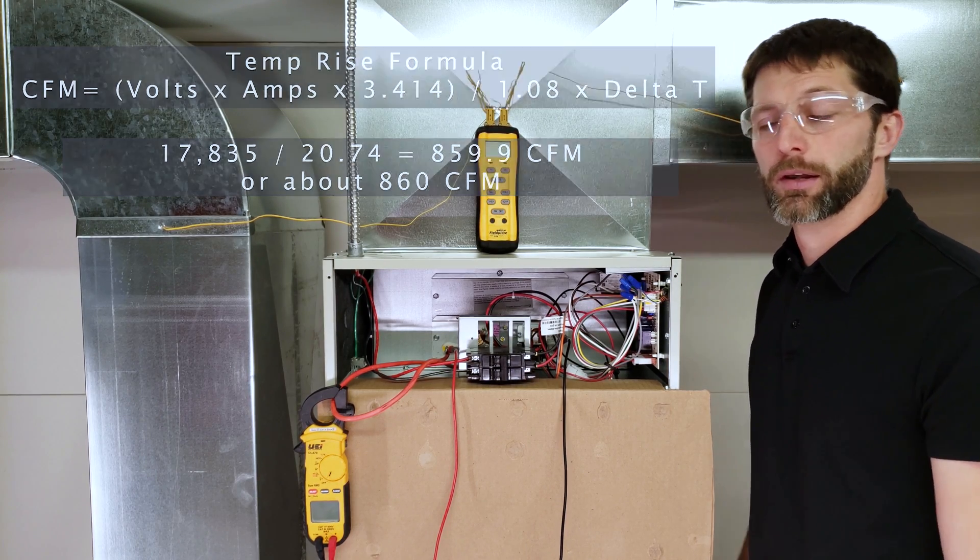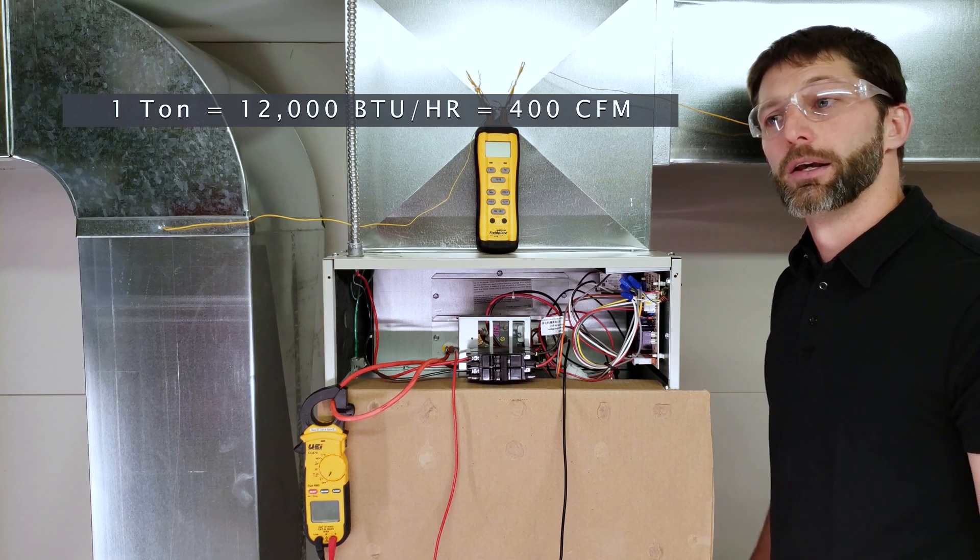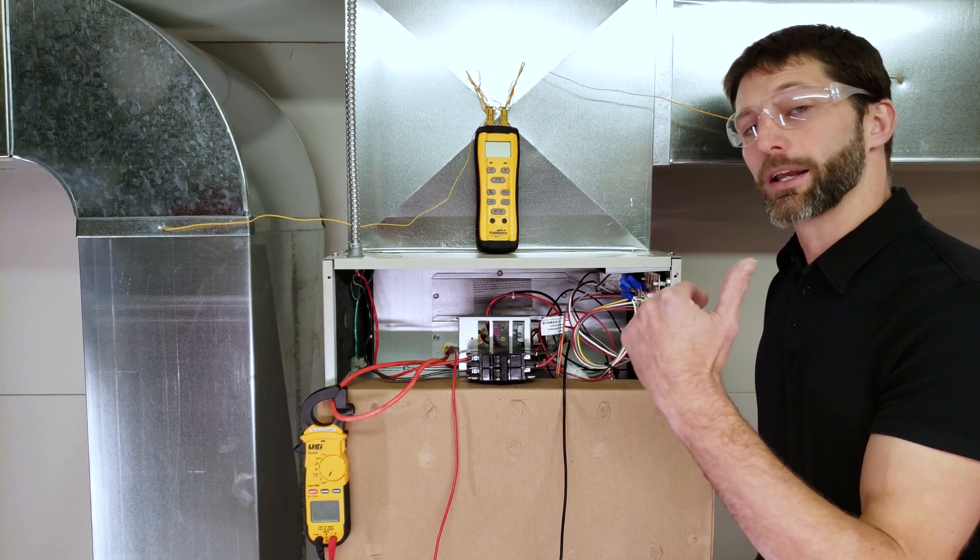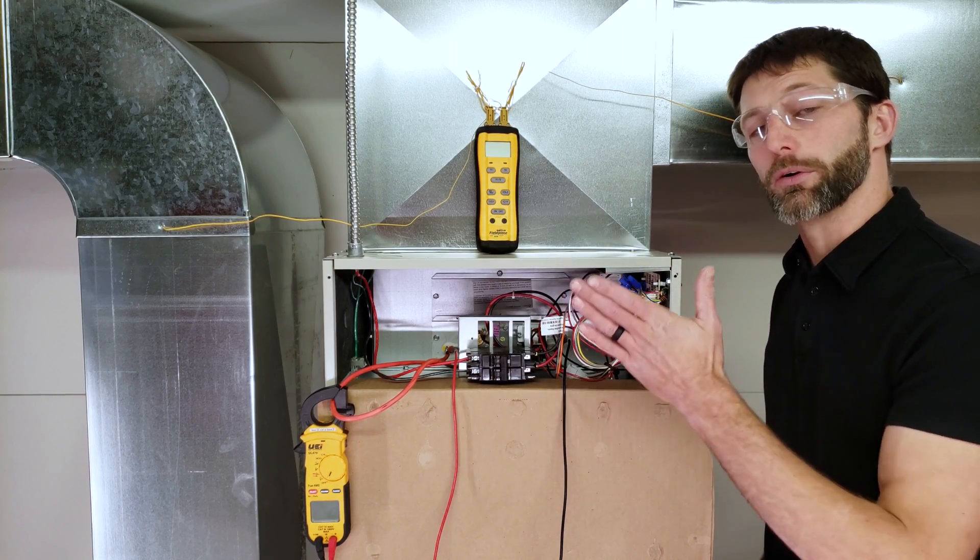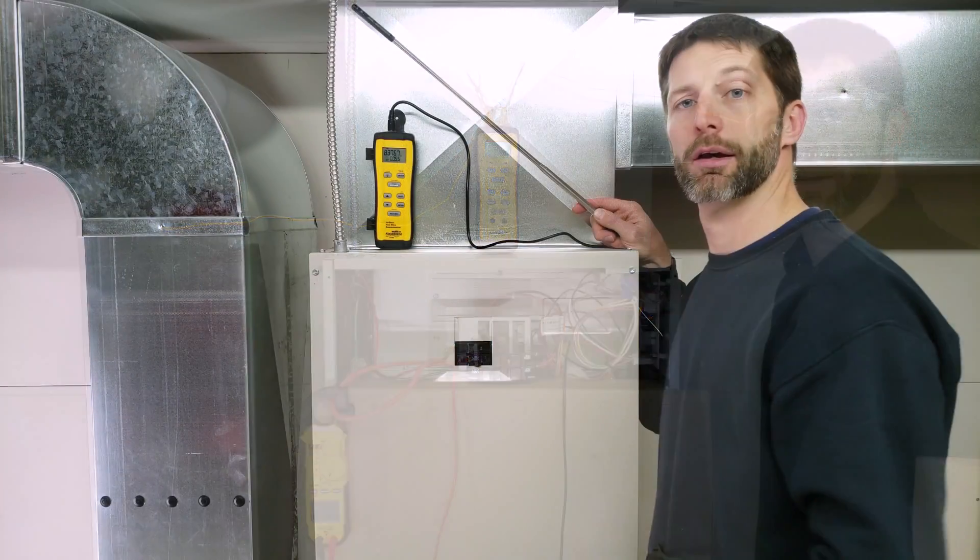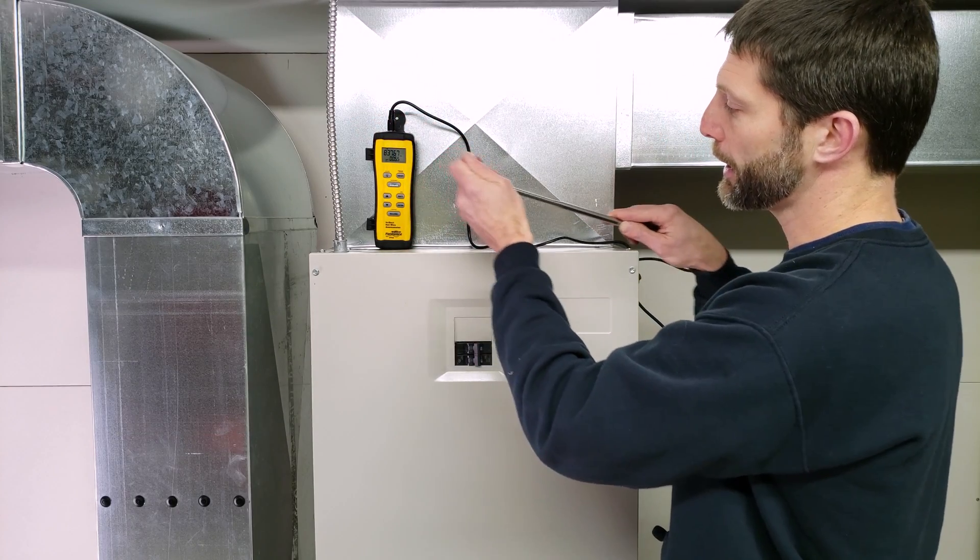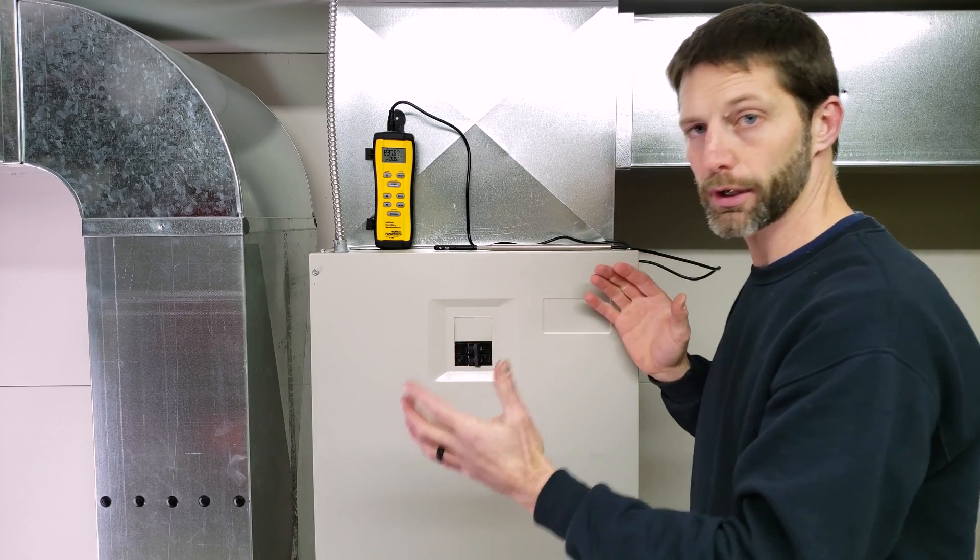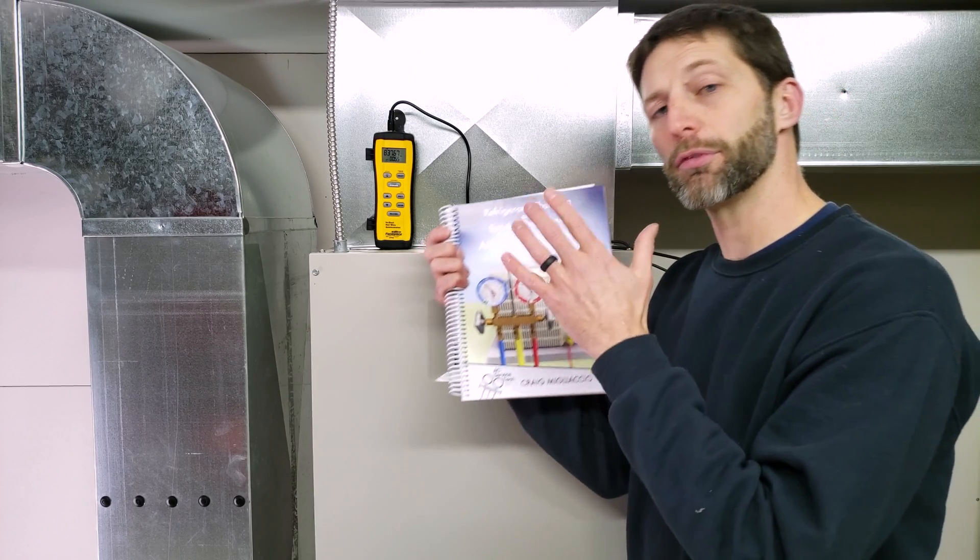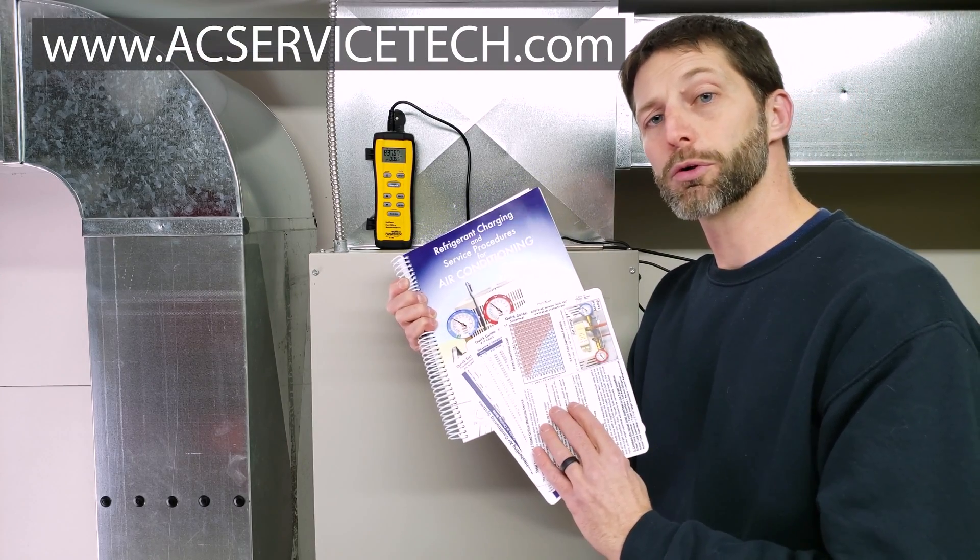For every ton of capacity, you want about 400 CFMs of airflow for a cooling system—say 350 to 425 CFMs. You could be on the lower side at 350 if removing a lot of humidity. We're at 430 CFMs per ton (860 CFMs divided by 2 tons). The CFM from the temp rise formula was very close to the in-duct anemometer reading, just slightly higher. This system has the correct airflow for checking refrigerant charge and troubleshooting. To learn more, check out our book on refrigerant charging service procedures, available at acservicetech.com and Amazon. See you next time at AC Service Tech channel.